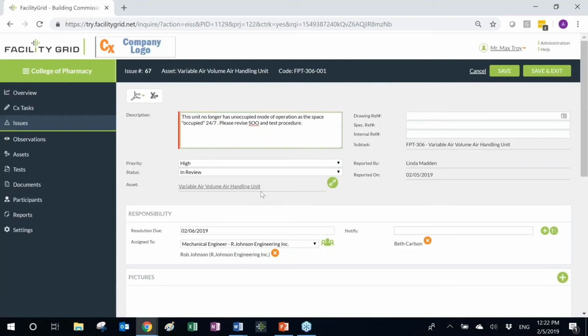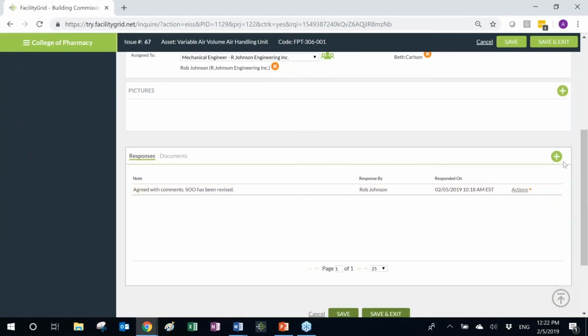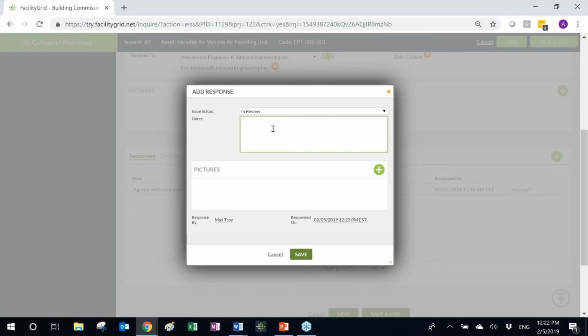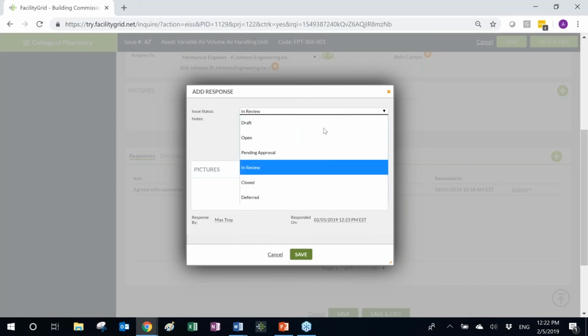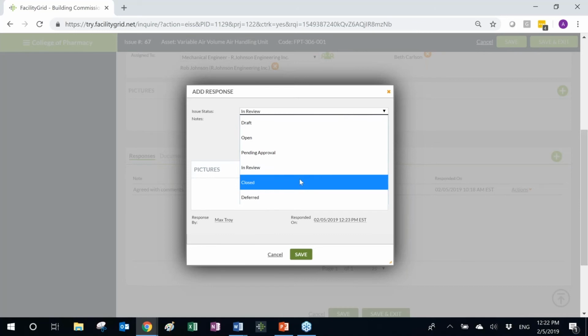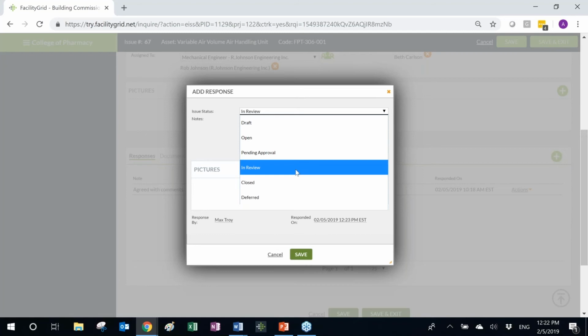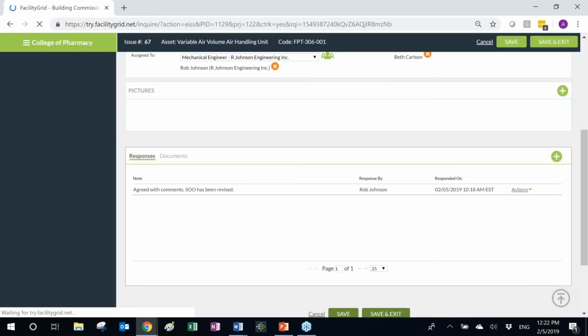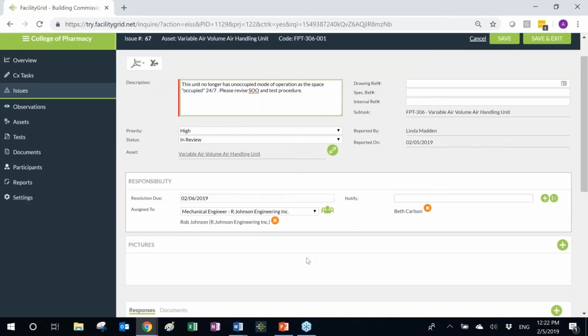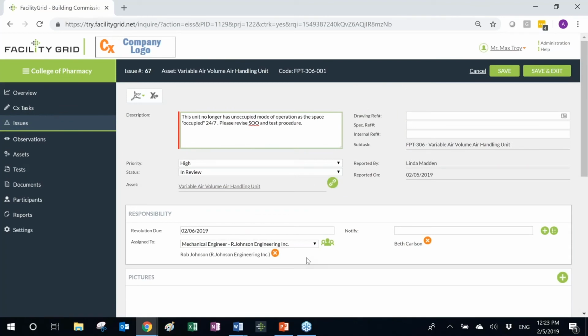At this point, I can simply provide the response and state that the issue has been addressed and the FPT procedure has been revised. In this case, I can also change the status of the issue. I can close it. Obviously, as a commissioning authority on the project, I have the permissions to close any issues. So I can close it, or I can keep it in review mode for the controls contractor to agree with my statements, with my responses, and close it. So when the controls contractor gets notification from the commissioning agent, then he or she can go in and close this particular issue.